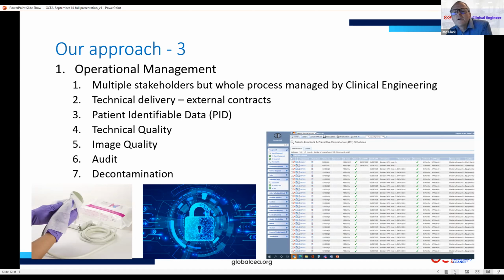Another important consideration when using external agents as part of any maintenance regime, whether it's ultrasound or anything else, is what happens with patient identifiable data. Many devices nowadays will gather data on our patients or be linked to our patient management systems. But this is particularly the case with any imaging system, any imaging device. So it's therefore important to have a process in place to control how we manage patient identifiable data, to make sure it's sanitized or removed before we give control of the ultrasound machine to an external agent.